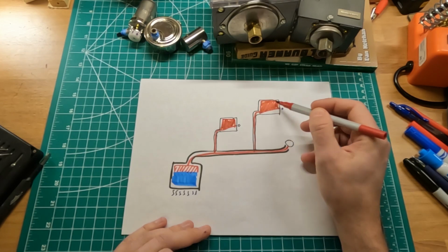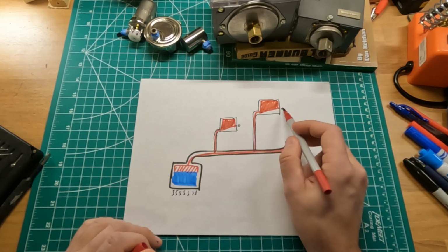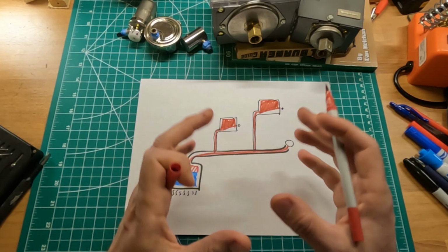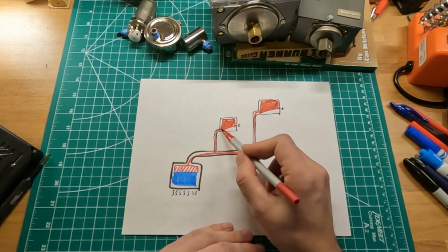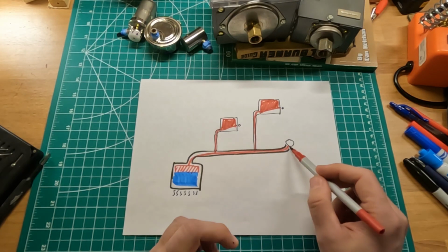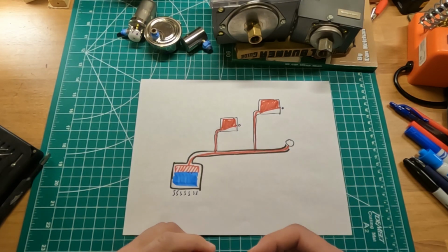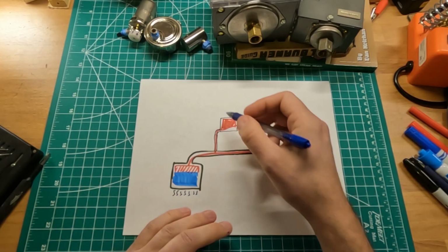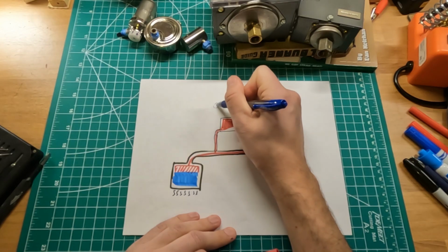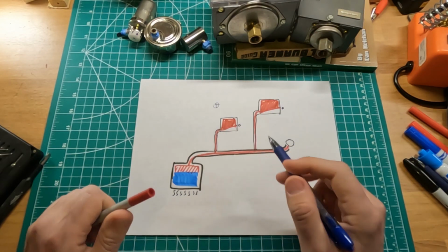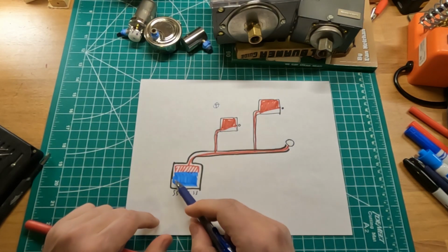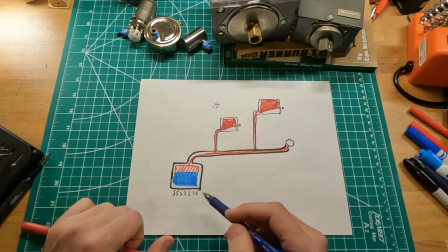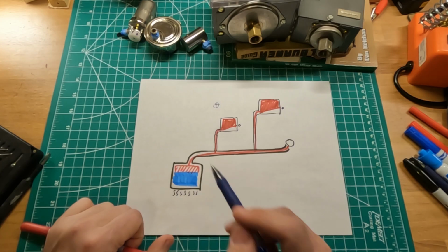And then as the steam hits the internal mechanism of those air vents, they close, trapping the steam inside the radiators, and likewise trapping steam inside the main pipe. So what ends up happening is, let's say we have a thermostat in one of those rooms, and that thermostat still keeps on calling for heat. Because of that, the boiler doesn't care. The boiler is being asked to produce heat, so it keeps on producing heat, namely, keeps on producing steam.